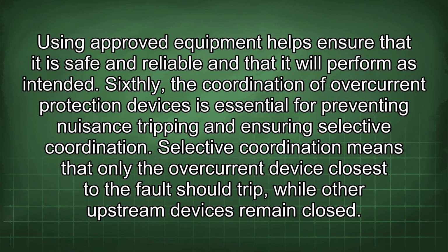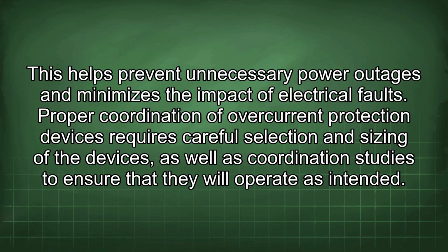Sixthly, the coordination of overcurrent protection devices is essential for preventing nuisance tripping and ensuring selective coordination. Selective coordination means that only the overcurrent device closest to the fault should trip, while other upstream devices remain closed. This helps prevent unnecessary power outages and minimizes the impact of electrical faults. Proper coordination of overcurrent protection devices requires careful selection and sizing of the devices, as well as coordination studies to ensure that they will operate as intended.